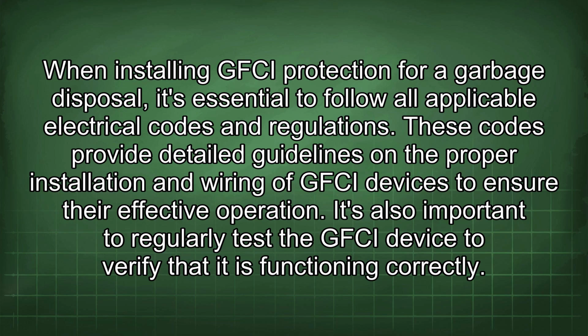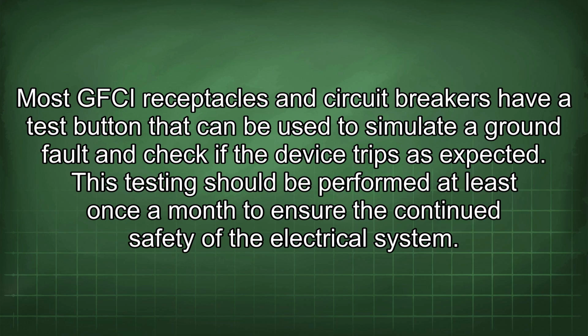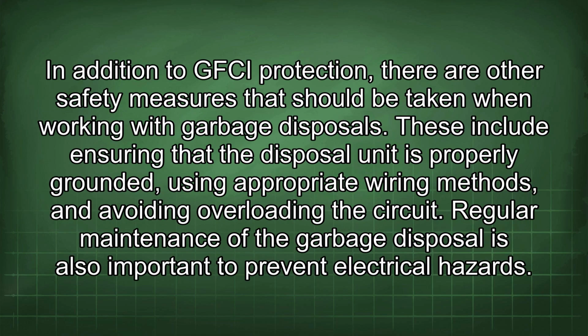It's also important to regularly test the GFCI device to verify that it is functioning correctly. Most GFCI receptacles and circuit breakers have a test button that can be used to simulate a ground fault and check if the device trips as expected. This testing should be performed at least once a month to ensure the continued safety of the electrical system. In addition to GFCI protection, there are other safety measures that should be taken when working with garbage disposals. These include ensuring that the disposal unit is properly grounded, using appropriate wiring methods, and avoiding overloading the circuit.